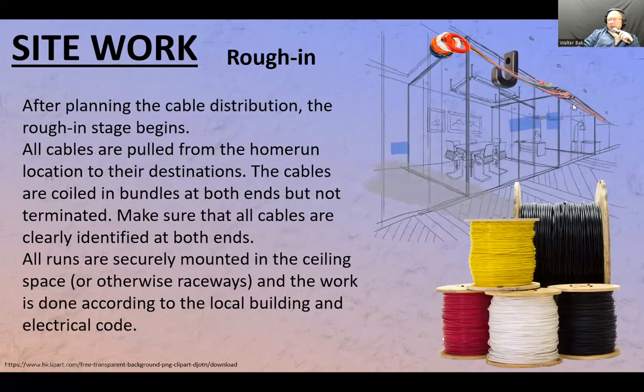If you bundle up the wires, let's say from the LAN room, you can find a common point to branch them off, which is the most efficient way to do this job. If you bundle those wires instead of pulling them one by one, you pull the whole bundle—maybe 12 wires, which isn't that uncommon, or even 15 wires depending on the gauge. I wouldn't pull 15 wires of Cat 6A at once, but Cat 5E, yeah, 12 to 15 wires has been done, not very uncommon. Then, instead of doing 15 trips, you're just doing one trip of 15, and from here you're branching out.